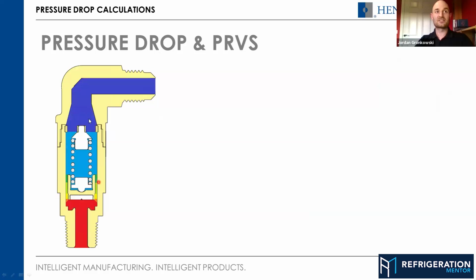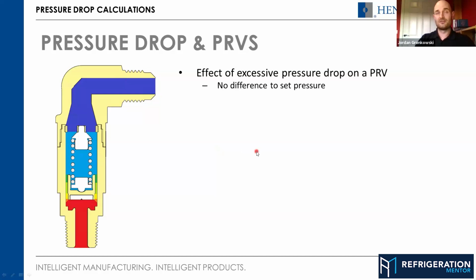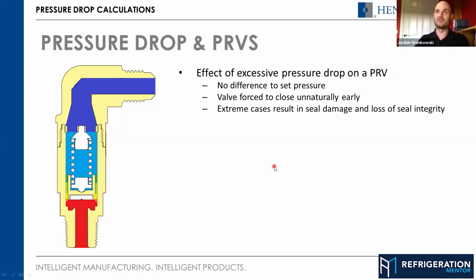When the valve opens, this is a simplistic rendering of what actually happens. So as the flow accelerates through various portions of the valve and geometries, the pressure effectively drops. So you start off with red, through orange into the blues and out the top. And this is how the valve is designed to behave. What's the effect of excessive pressure drop in a PRV? So first of all, if you've got pressure drop in the inlet or the outlet, there's no difference in set pressure. If you've got a long pipe that puts excessive pressure drop on the valve when it's flowing, it doesn't change the set pressure of the valve at all. So the valve will still open at the correct pressure. But what will happen is that the valve's forced to close unnaturally early, and it's not operating as designed. So in extreme cases, it's very similar to what we talked about with the chatter, with the oversizing. It can result in seal damage and loss of seal integrity.